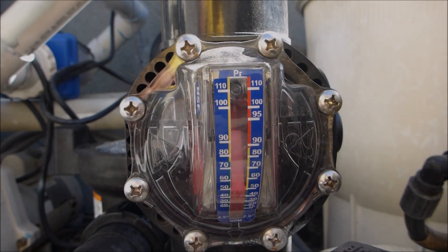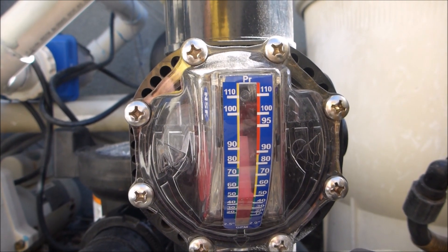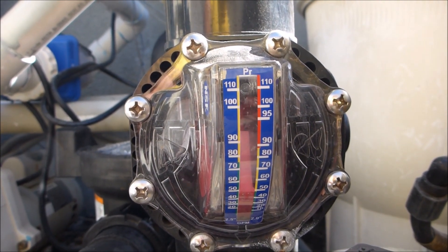The best way to set your run time and RPMs on your variable speed pump is to install a flow meter like this FlowVis here. That way you know exactly how many gallons per minute is moving through the pool at the set RPM.